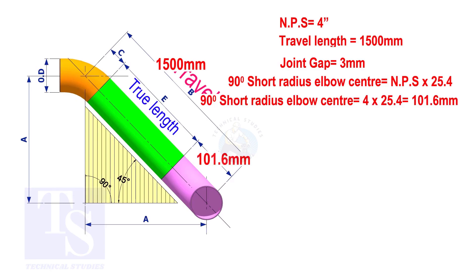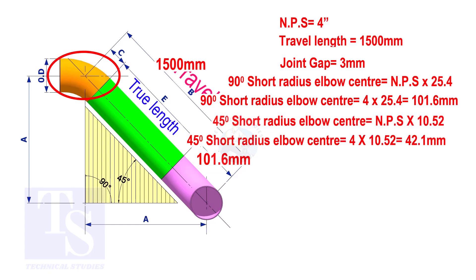To calculate the elbow center of a 45 degree short radius elbow, multiply the nominal pipe size by 10.52. The answer is 42.1mm.